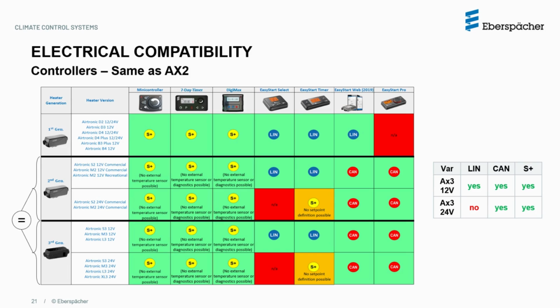As for electrical compatibility with different controllers, it's the same as with the second generation, both for 12 and 24 volt heaters. With analog controllers, such as the Minicontroller and the Digimax, we can't use the external temperature sensor, as I just mentioned, and no diagnostics is possible. On the 24 volt versions, LIN is not available, so you can't use the Easy Start Select at all, and the Easy Start timer only works with S+ signal. The big advantage that started in the second generation and continues now is the use of CAN-based more advanced controllers, such as Easy Start Pro, that has several advantages and new features compared to their predecessors.